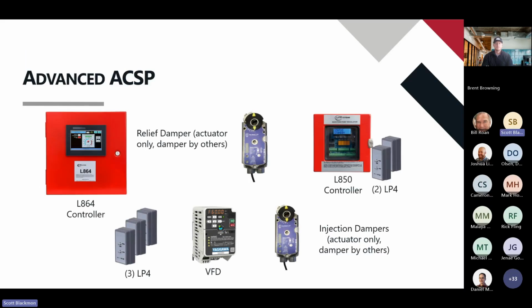Now, this system works great for buildings up to about 12 stories. But when we get beyond 12 stories, our natural stack effect becomes greater than 0.3 inches between the top and bottom floor. So what we have to do is introduce our L850 controllers with pressure transducers.